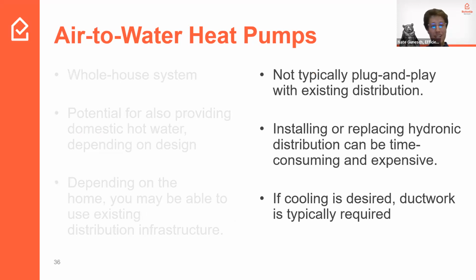But these are typically not plug and play, because most of us already have cast iron radiators or fin tube, which aren't designed for the 110-120 degree water from an air to water heat pump. They're used to 180 degree water from a traditional boiler. This is part of why we get such high efficiencies, but it makes it challenging to just swap in directly.